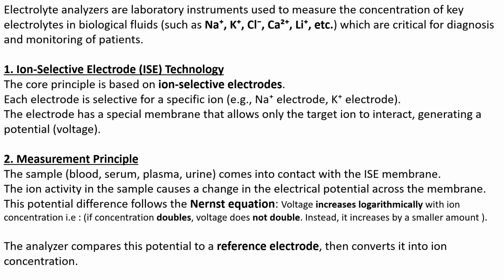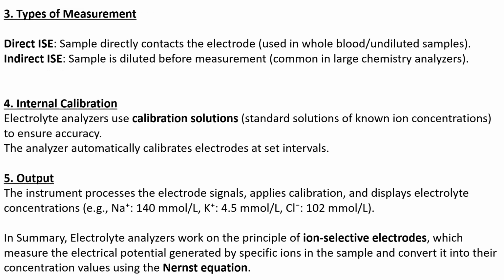The measurement principle. The sample, the blood or the serum, comes into contact with the ISE membrane. The ion activity in the sample causes a change in the electrical potential across the membrane. The potential difference follows the Nernst equation, which states the voltage increases logarithmically with ionic concentration. The analyzer compares this potential to a reference electrode and converts it into ion concentration.